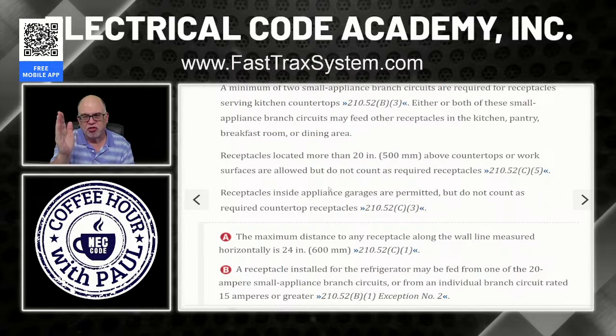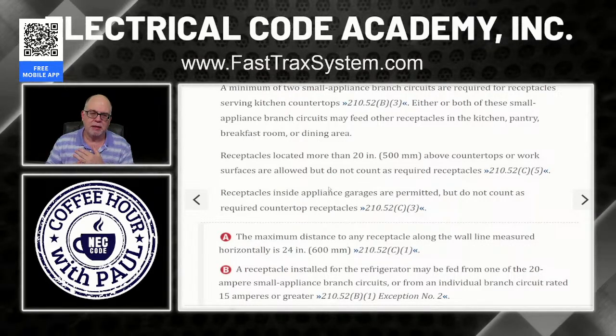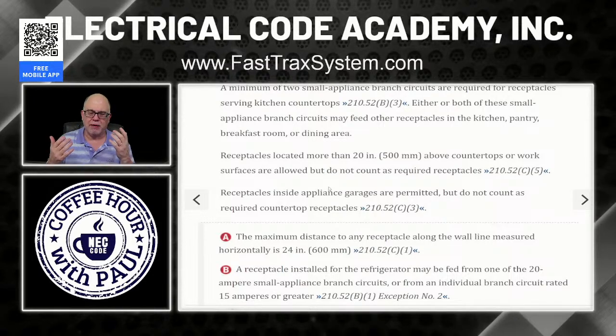So you'd have to start your measurement at the edge of that appliance garage, and then you'd have to have one within 2 feet, right? Because you could put receptacles in there, but again, they're inside of a cabinet, like a cupboard, and they don't meet the spacing requirement. You can have extra ones in there if you want. That's fine, but they won't meet the spacing rules.